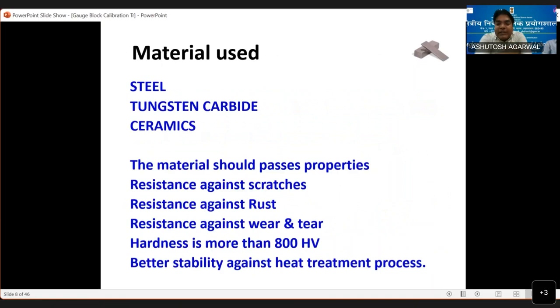So what are the materials used to make this gauge block? There are three basic materials. One is steel, then tungsten carbide and ceramic. So why do we choose those materials? Because we need the material to be resistant against scratch, so there should not be any scratch. Steel is a hard material, tungsten carbide is even harder. Ceramic is wear resistant, but it can break.